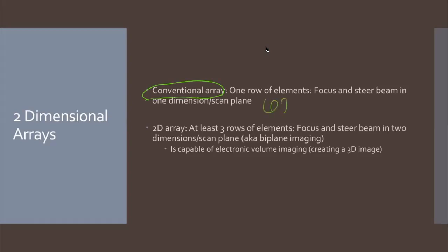On page 62, image A shows you that. I may or may not have referenced this to you guys before. I know we can't see the PZTs inside of the transducer, but you can see how all the pulses coming out of the transducer are all next to each other. It's like one after another. They're all in one straight line. And so next to image A, I want you guys to write down that this is a conventional array.